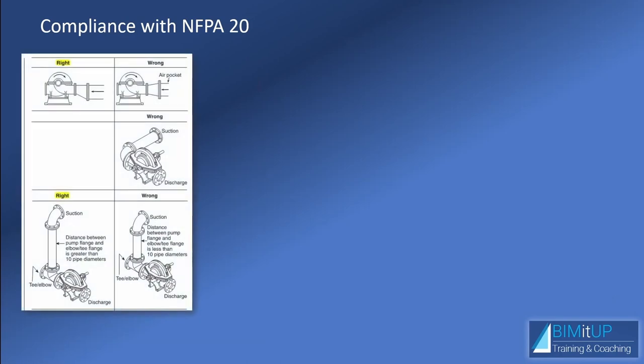A couple other things from NFPA 20, as I mentioned a couple of times: that reducer at the suction should be eccentric to avoid those air pockets. So this would be a wrong installation. Another thing that you'd want to avoid is to have a horizontal turn immediately before the suction flange, because that creates turbulence and it may damage the impeller. So this would be the right way of piping.